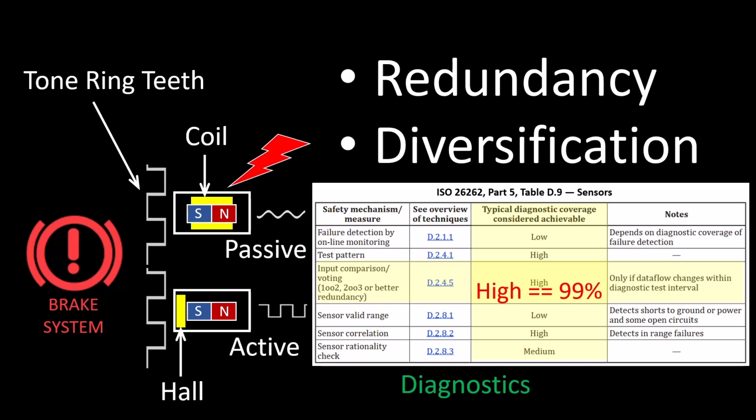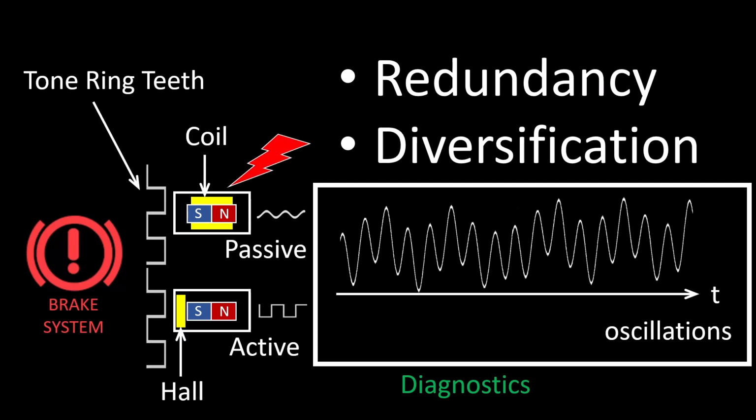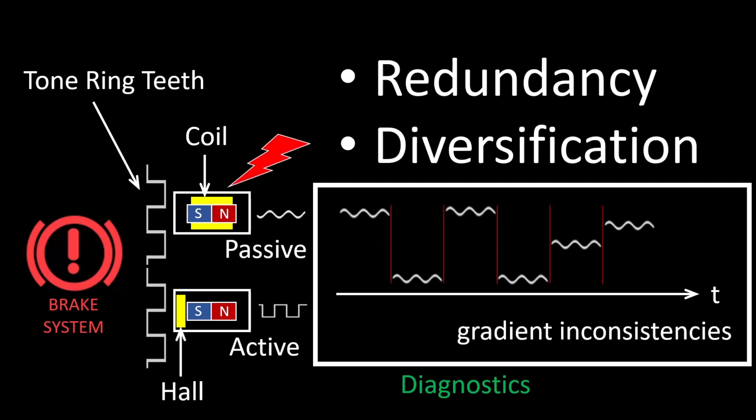What exactly should these diagnostics look for? According to the standard, you should check for stuck-at faults, drifts, oscillations, range violations, and gradient inconsistencies.